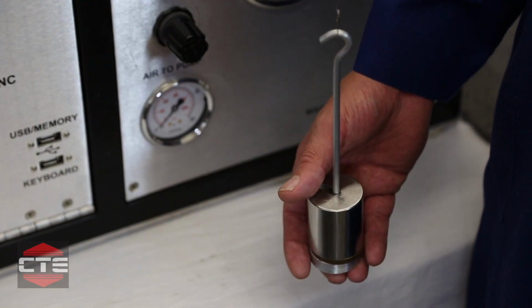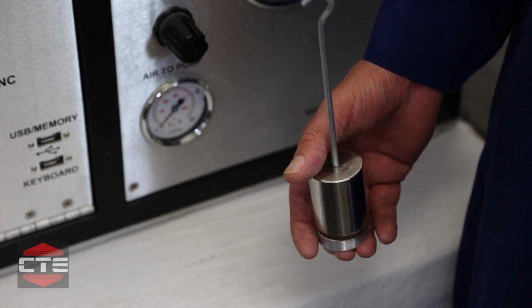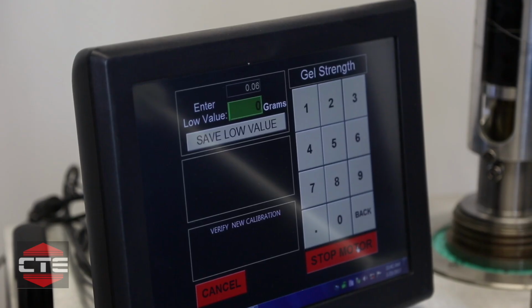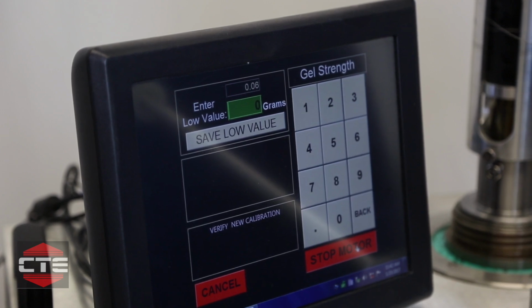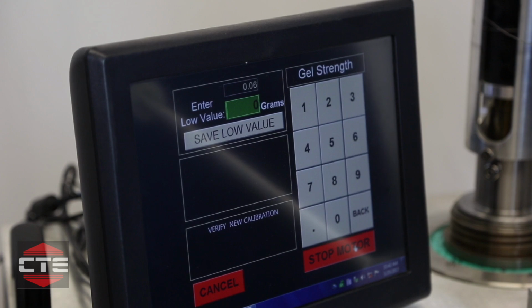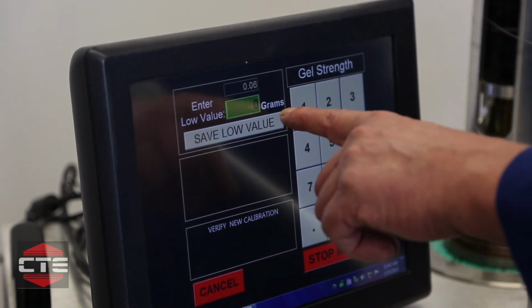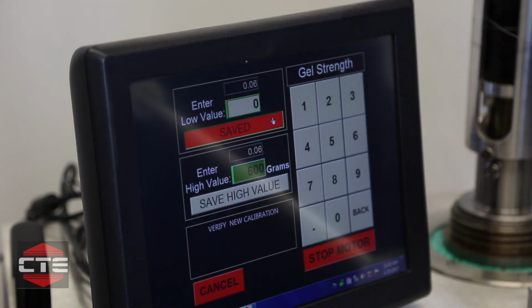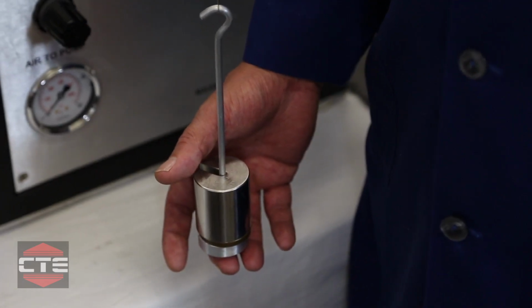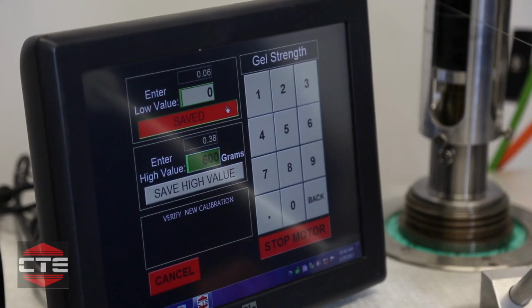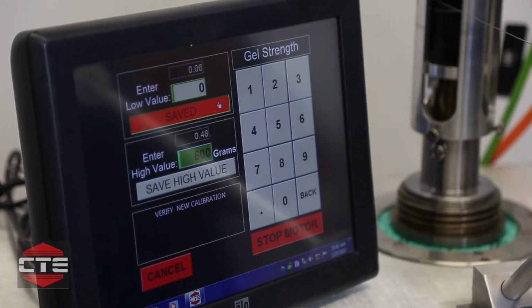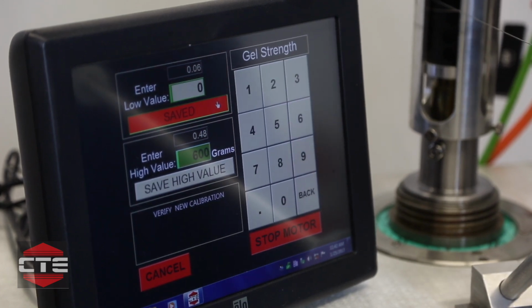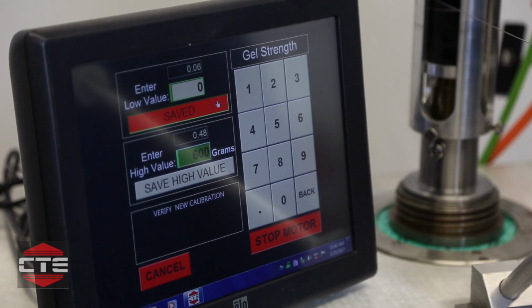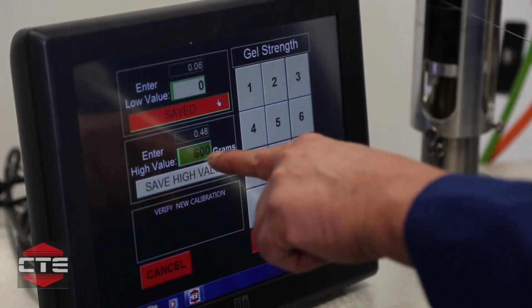Our next step is to lift the weight off of the motor to where you have no torque on the motor at all. You will watch your raw value fall, and when it stabilizes to the bottom end, we're going to save that low value that's automatically entered into your green box there of 0. And my raw value is 0.06, and we're going to save that for 0. At the completion of that step, we're going to reinstall the 600 grams. Our raw value will go up, and it should match what you had when you were letting the initial 600 grams stabilize to one value. That should be the value you're looking for. In my case, it was 0.47, and I am at 0.48, stable, and we're going to save the pre-entered 600 grams.